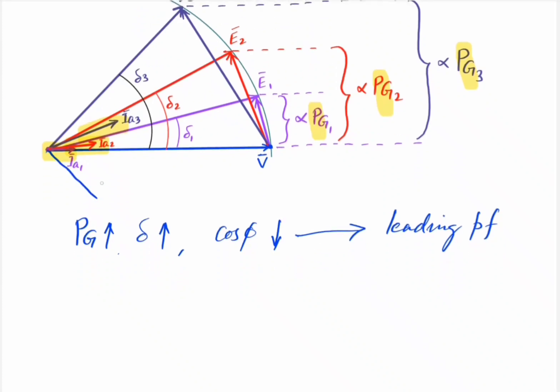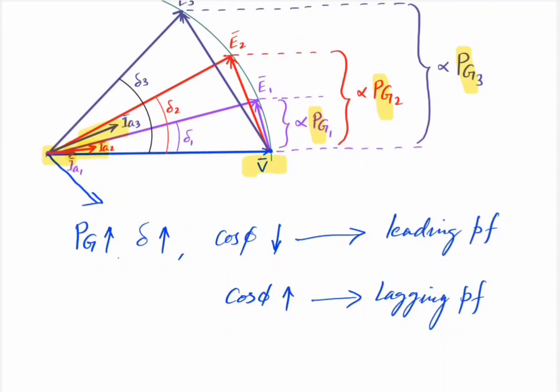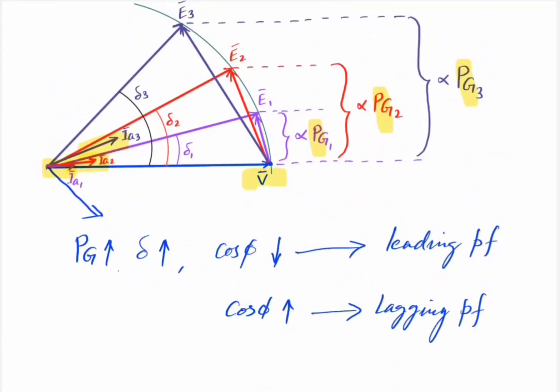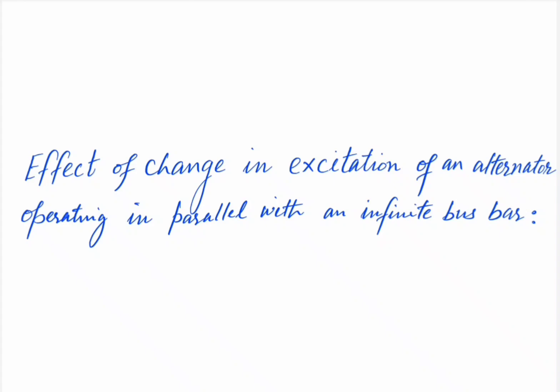For the lagging power factor case, that is when Ia lags the terminal voltage V, the power factor cos φ increases with increasing mechanical input. Once the active power output of the alternator is adjusted to the desired value, the corresponding governor set point is fixed. Now, after fixing the governor set point at the desired active power output, we will study the effect of changing excitation, keeping the active power output at that desired value.